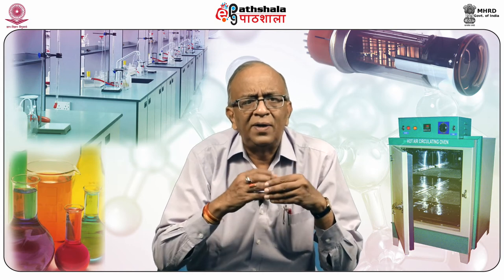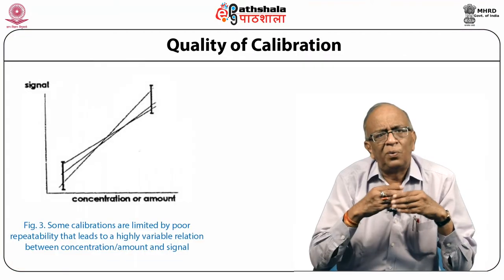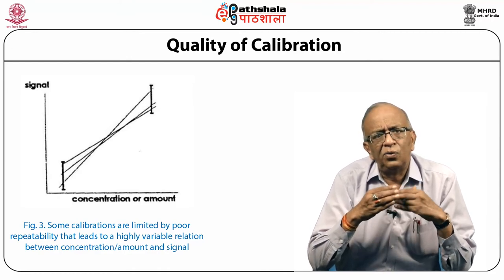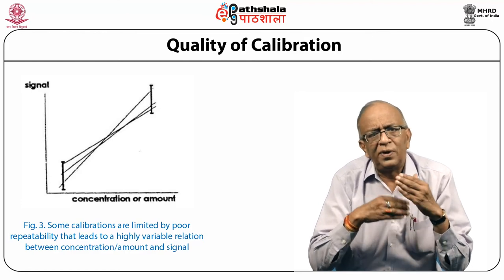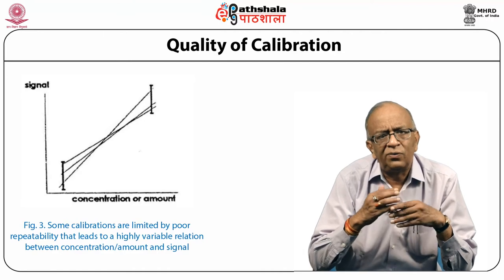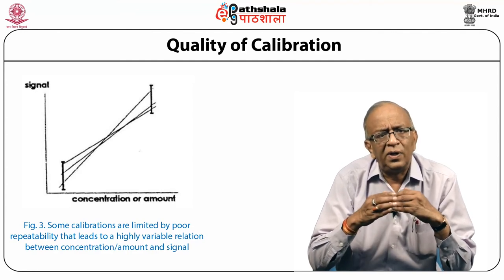No quantitative measurement can therefore be better than the intrinsic quality of the comparison process called calibration, and there are a couple of ways to improve this comparison process. One factor is the repeatability of the measurement itself — the process should be repeatable and reproducible. If the measurement gives highly variable readings, it will tend to do so both for standard and the unknown. The signal size is therefore poorly defined, leading to poor predictions of the measurement.